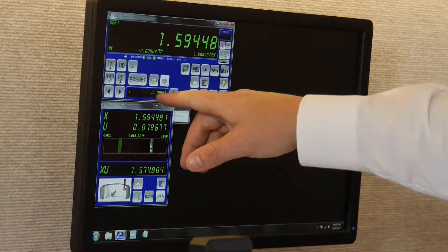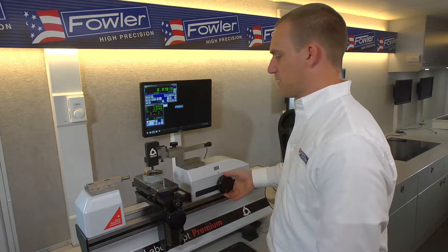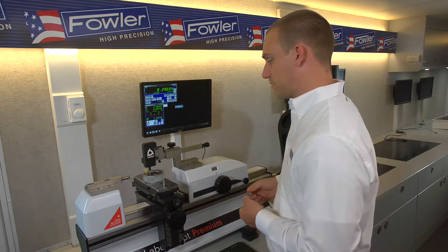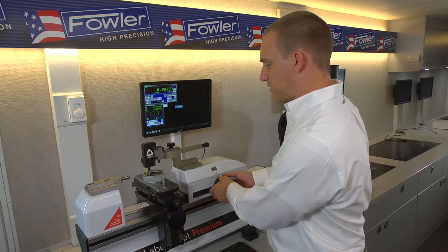Once the ball constant is locked in as a preset, I'll just use the same ring as an example. Normally we'd be going to a less accurate ring to actually go in and calibrate something, but we just want to show that the measurement works.